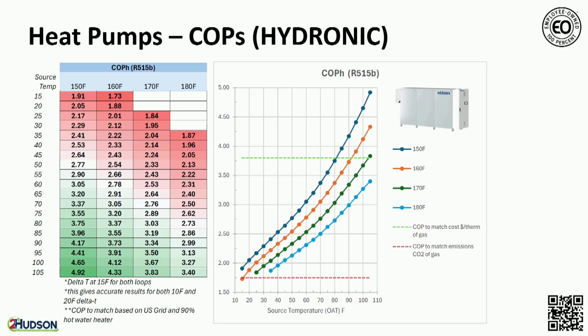Another important factor, and you'll see from these trend lines, as the COPs drop, depending on what the temperatures you're working with, capacities will also change. So if you are given a heat pump that's rated at 200 MBH, and you change the temperatures that it's working with, you will also change the capacities that are available from that heat pump.